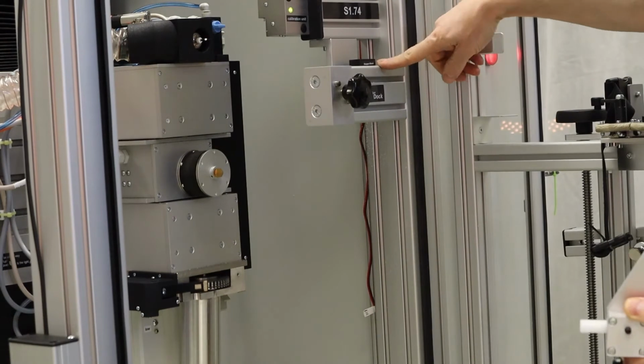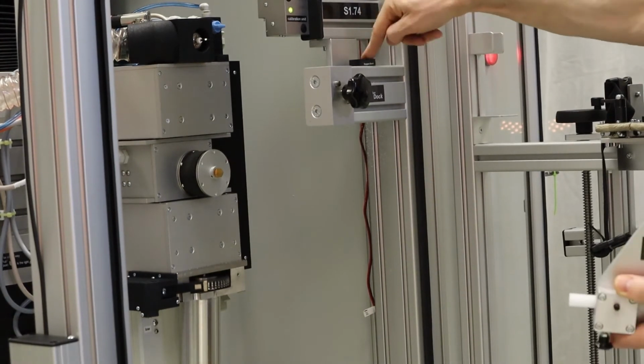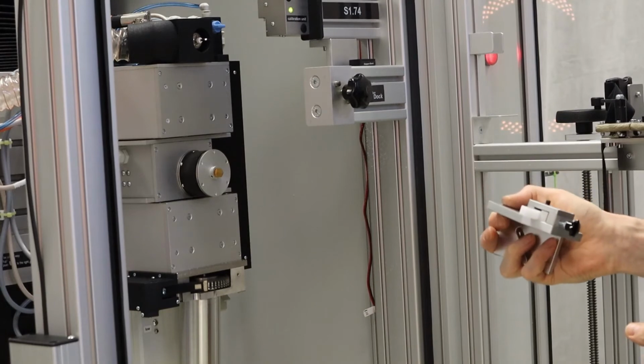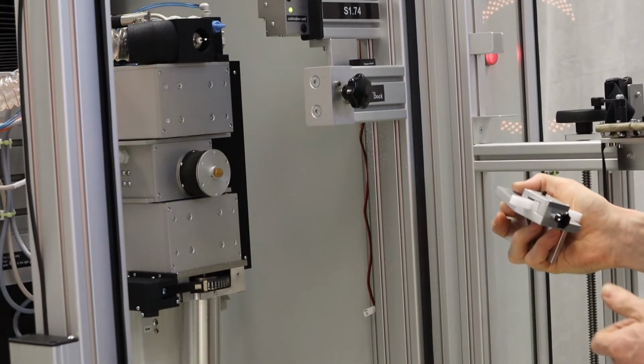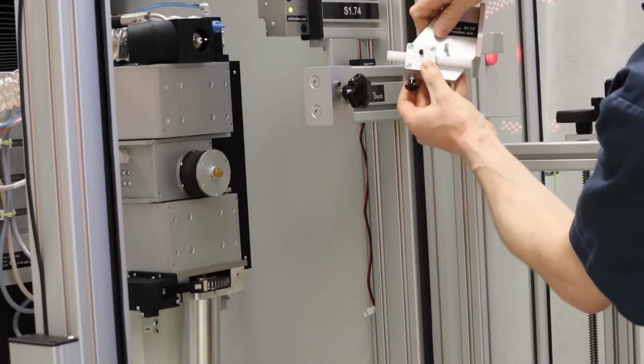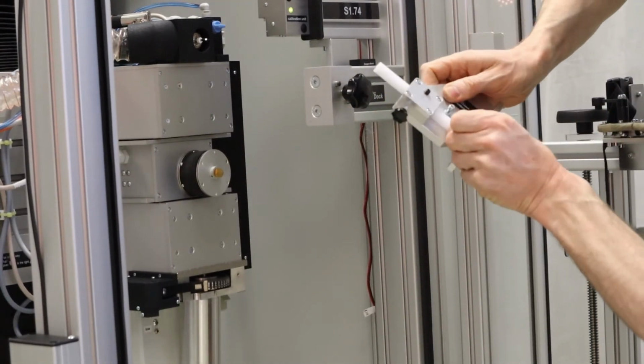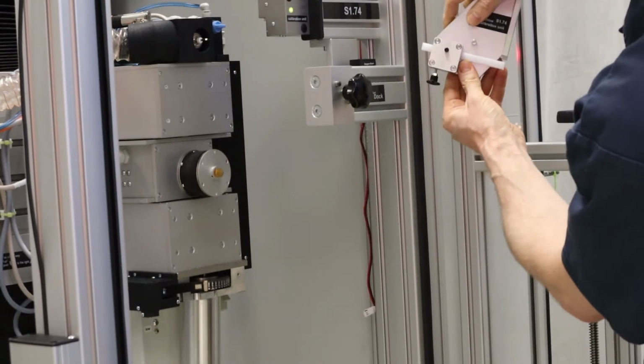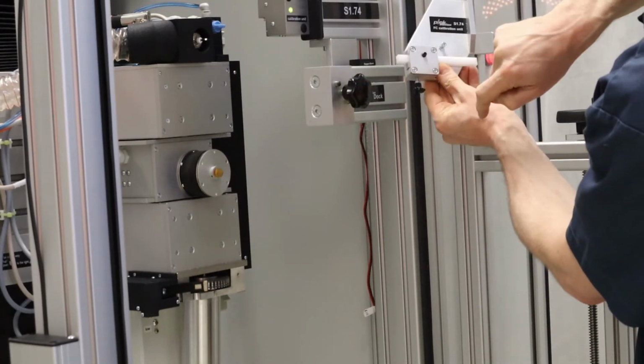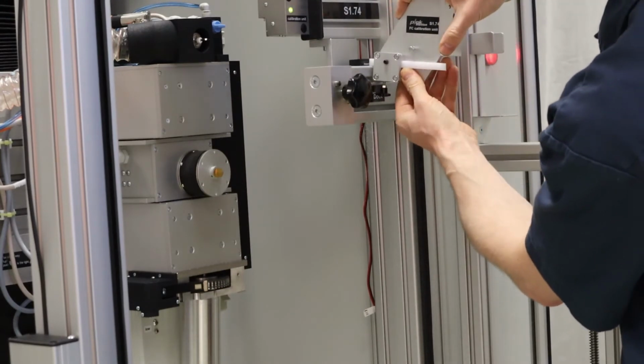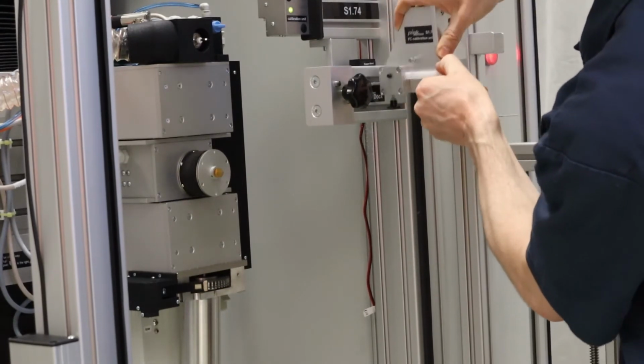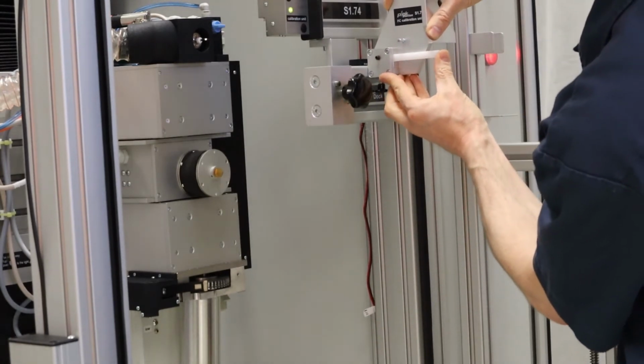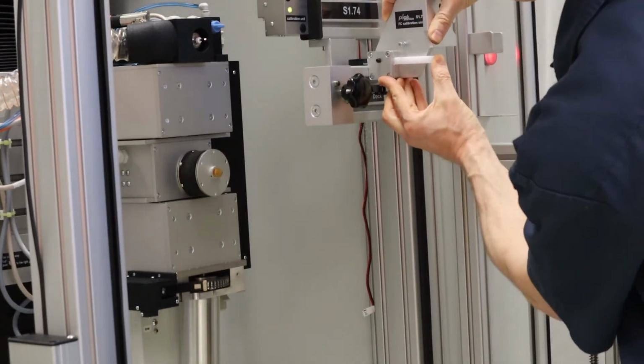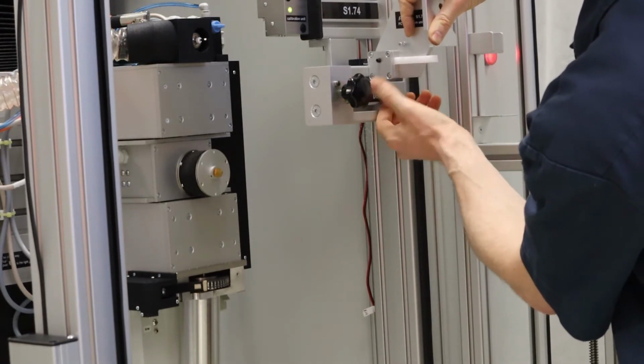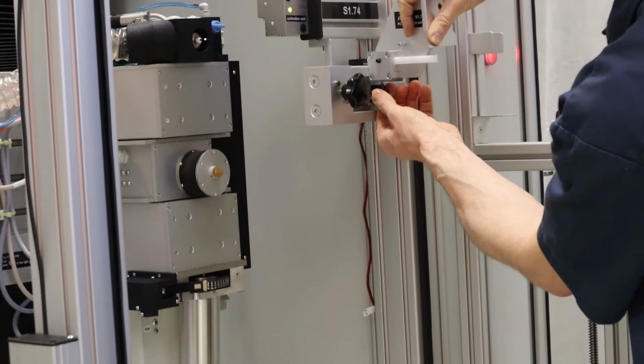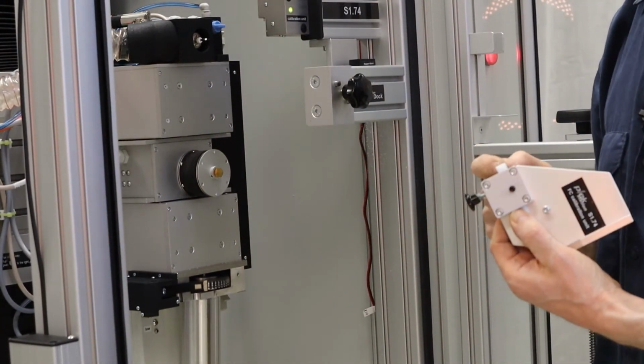On top of the dock, there's a stopper block, which is a black piece, and with that you can set the position correctly. So if you loosen the star knob on the bottom, the stick can be moved. You place the FC calibration unit, this part, up against the dock, and then you can push the stick up against the stopper block here. Okay? And then you tighten the star knob on the bottom, and then you see this distance is set correctly.